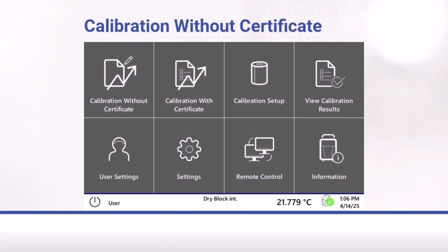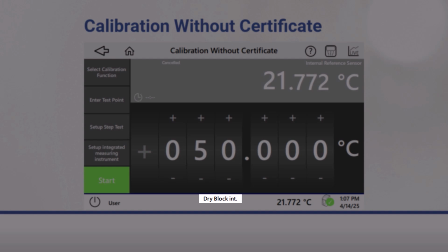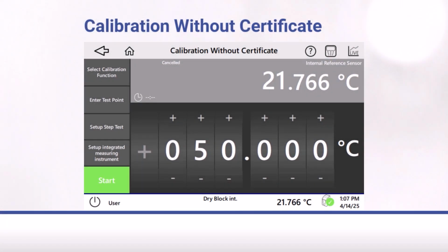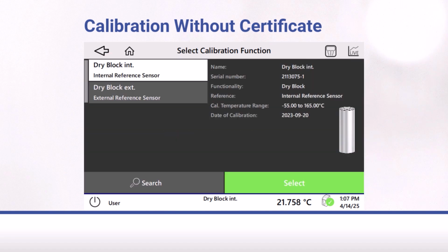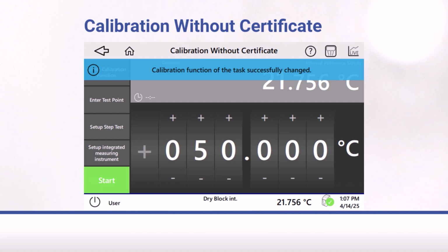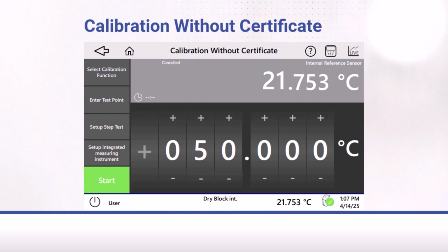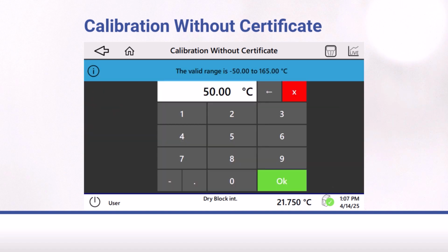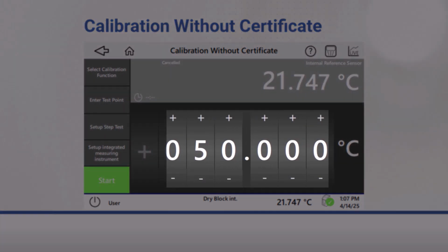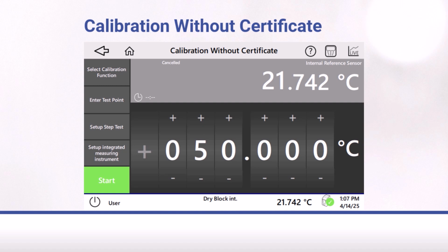From the main screen, tap Calibration without certificate. The current calibration function is displayed in the bottom bar. If you want to use a different function, tap Select Calibration function. Tap Enter Test Point. Enter the test point. You can also quickly change the test point using plus and minus. Tap Start to start the calibration.